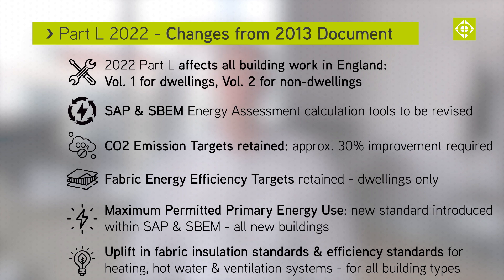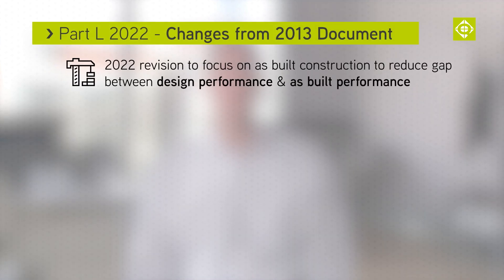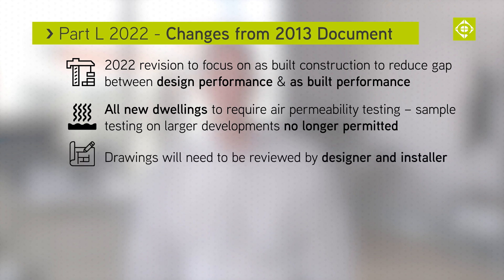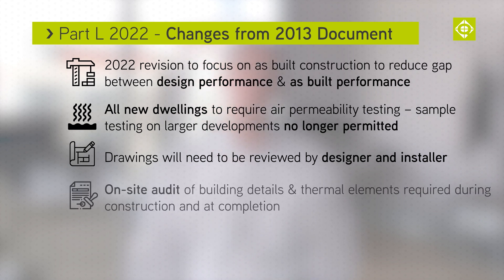The 2022 revision will place greater focus on as-built construction to reduce the gap between the design performance and the as-built performance. All new dwellings will require air permeability testing — sample testing on larger developments will no longer be permitted. Drawings will need to be reviewed by the designer and the installer, and an on-site audit of building details and thermal elements will be required both during construction and at completion for building regulation approval.